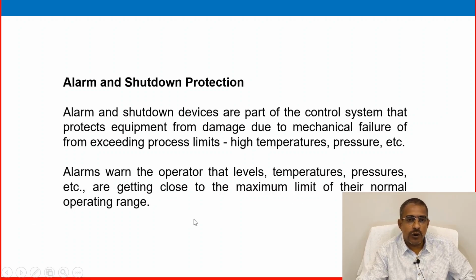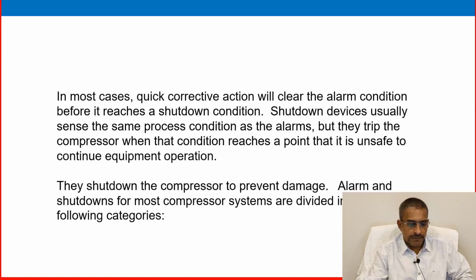The compressor runs within a normal operating range for various values, but if it deviates from the normal operating range, either very high or very low, it may seriously affect the compressor running condition and the equipment's internal parts. So to prevent that, alarm and shutdown system protections are provided to the compressor. In most cases, quick corrective action will clear the alarm condition before it reaches a shutdown condition. Shutdown devices usually sense the same process condition as the alarm, but they trip the compressor when that condition reaches a point where it is unsafe to continue equipment operation.